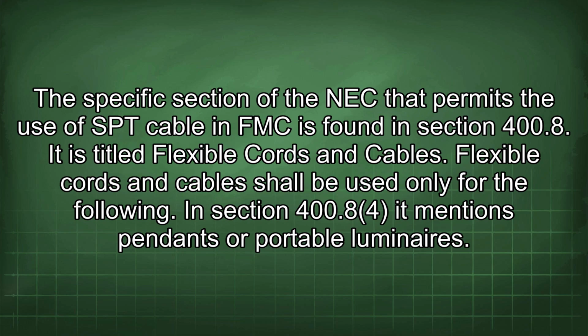The specific section of the NEC that permits the use of SPT cable in FMC is found in section 400.8. It is titled Flexible Cords and Cables. Flexible cords and cables shall be used only for the following. In section 400.8, it mentions pendants or portable luminaires.